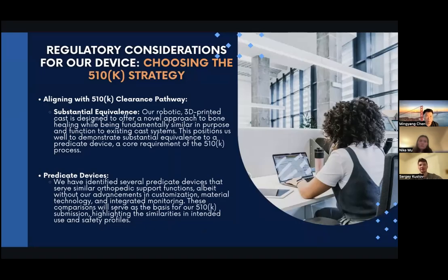And then for the regulatory considerations for a device and choosing the 510K strategy, what we want to showcase is that between the two, the PMA and the 510K strategy, if we want to commercialize something that is more innovative, but yet it's still a cast system, we don't really have to go the long way in the PMA structure, and we don't have to offer something.